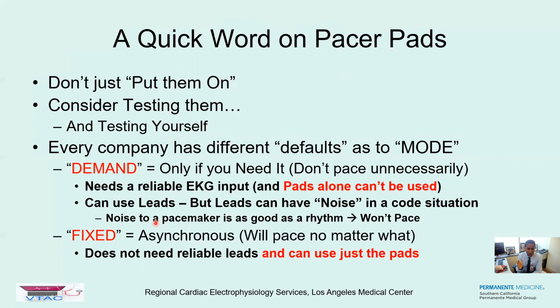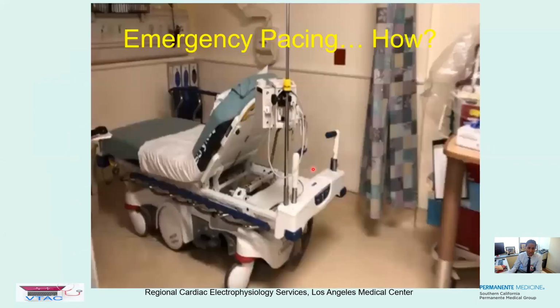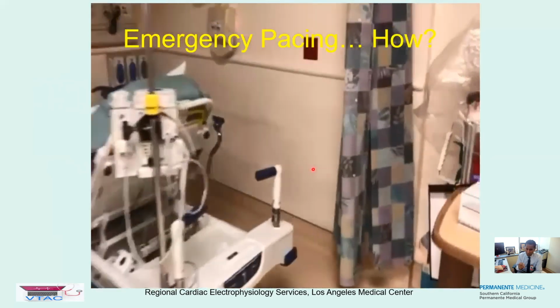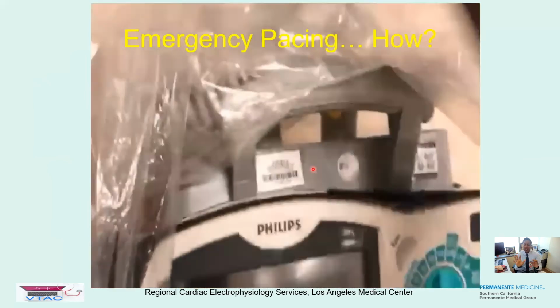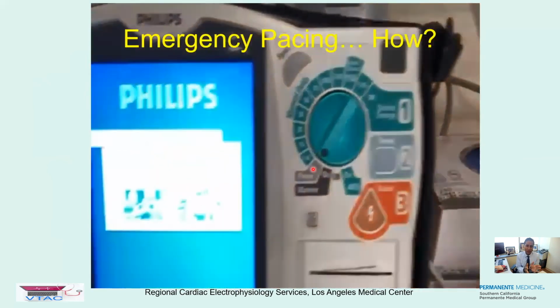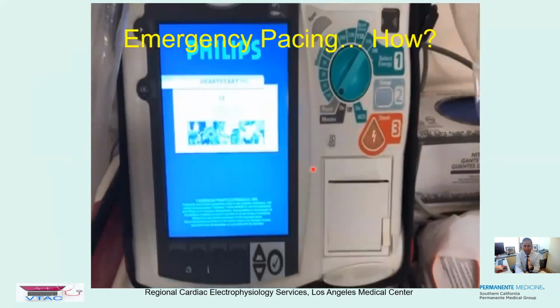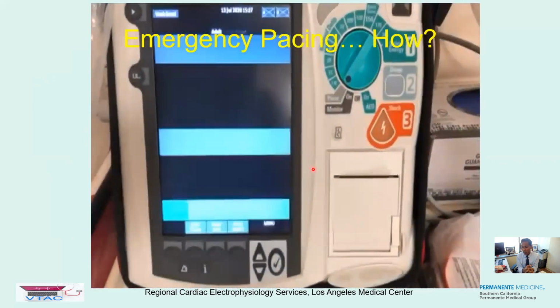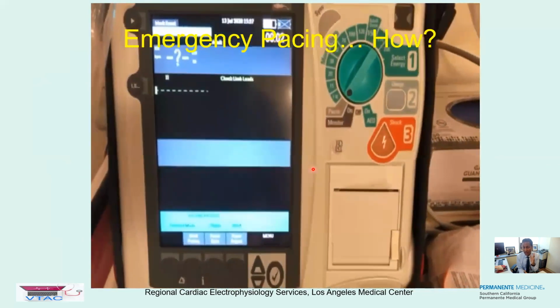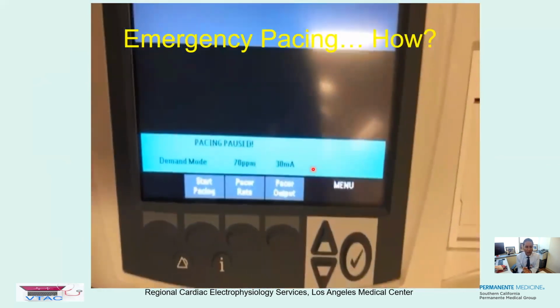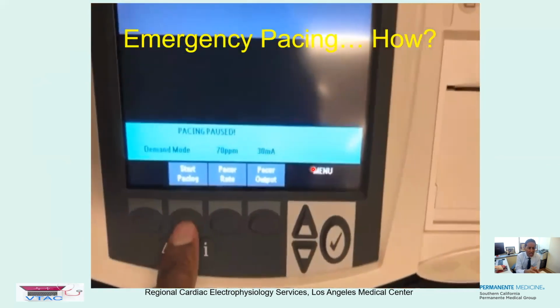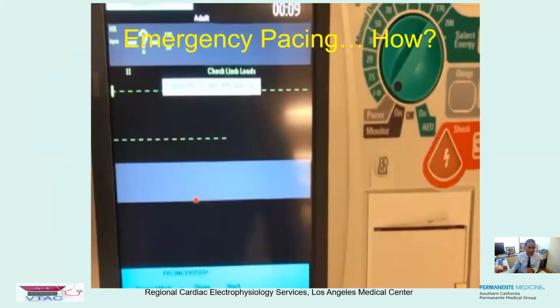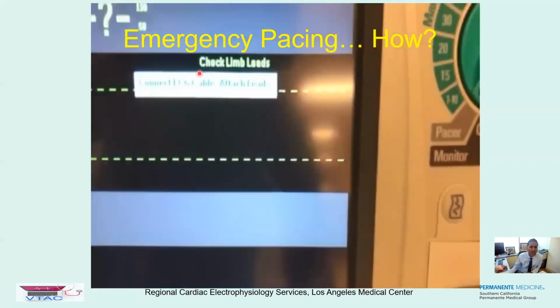So just learn how to change a device to an asynchronous mode. Imagine a patient right now is in asystole, okay? I'm calm right now and I'm turning it over to pacing. You would turn — we have Philips here, so I don't know what you have at your hospitals, but this is true for Medtronic, and I need to check with Zoll as well. So I push start pacing and you can see it says demand mode and it's not pacing. Here it says, check your EKG leads, right?